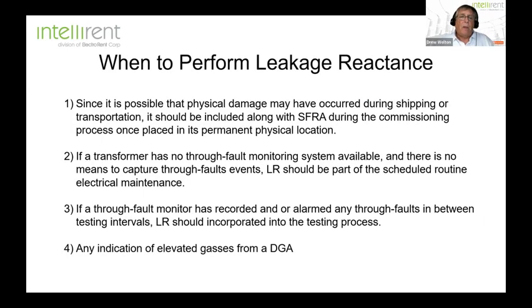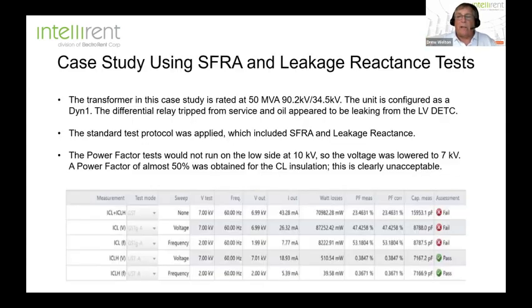Okay, so again, here's when we're going to perform it. We could always do it when we're commissioning the transformer. We can do it when your through fault monitor is recorded. Anytime we suspect there may be some physical damage to the windings. Now, if you see an indication based on those standards, then you'll want to do your SFRA, because that is really the fine tune in terms of finding mechanical damage.